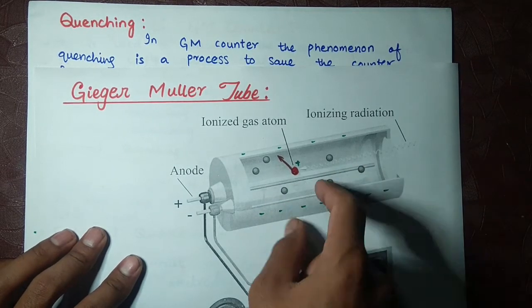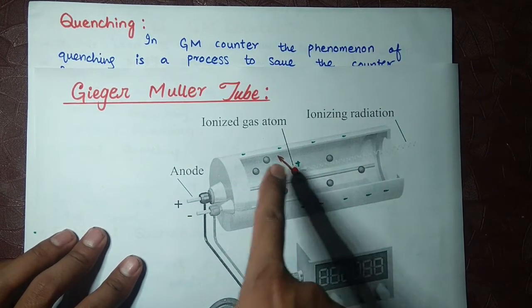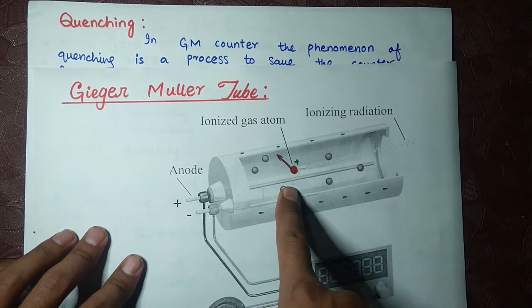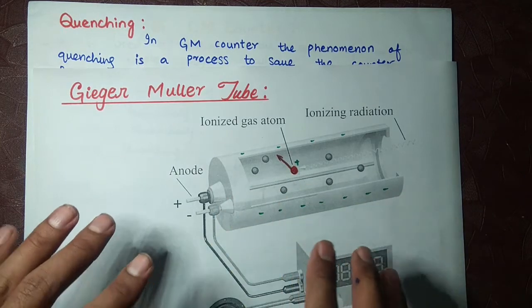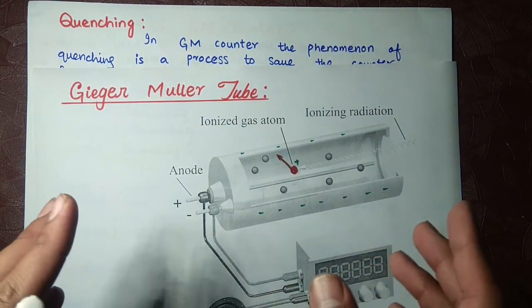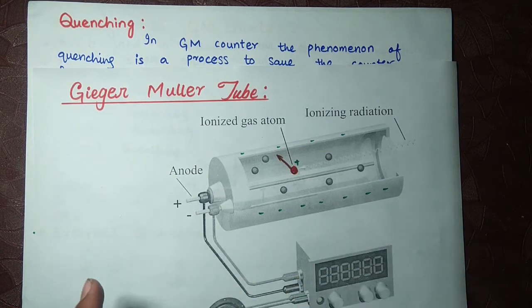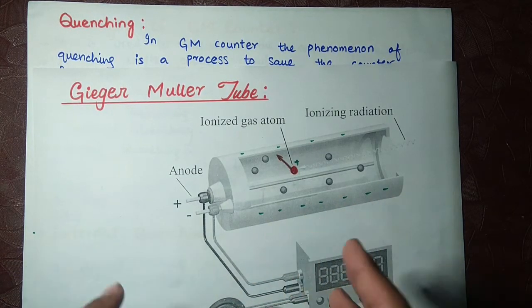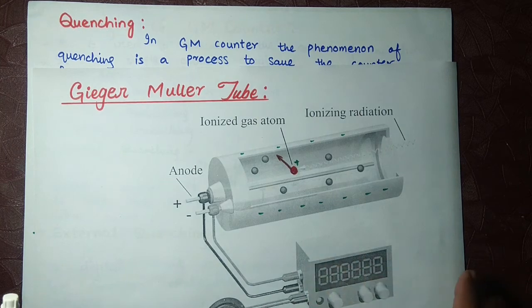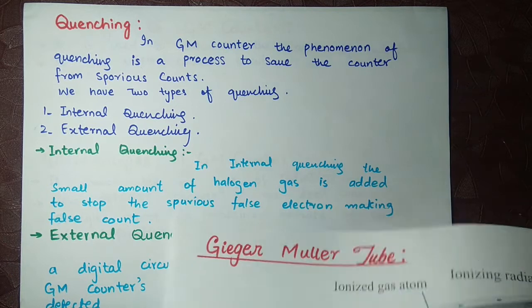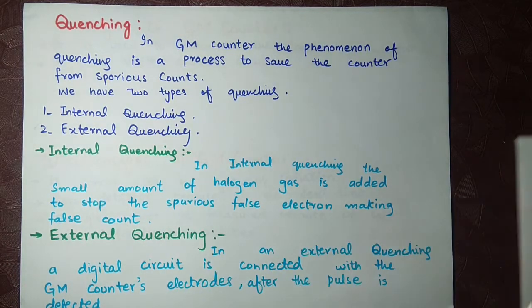When bromine absorbs the electron's energy, the electron has no kinetic energy left and cannot go to the anode. Because it cannot reach the anode, it cannot make a false count. This is how internal quenching works.